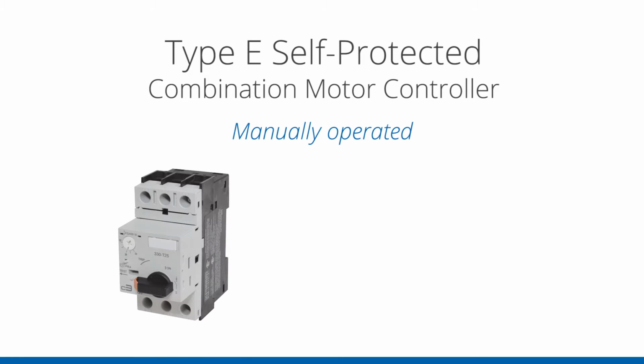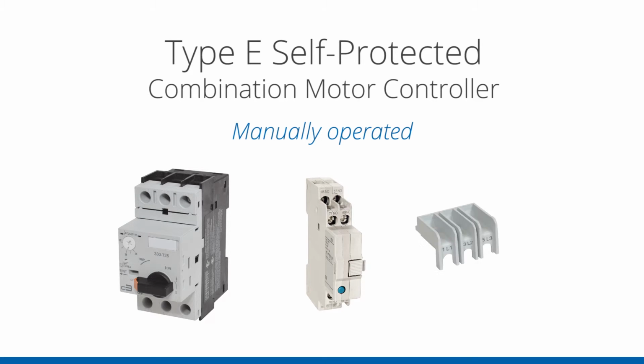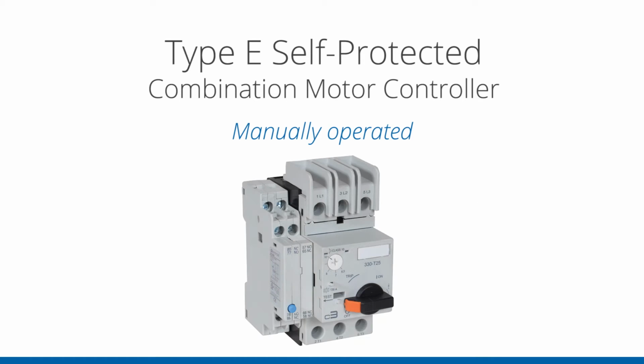Type E starters are listed as full combinations, meaning that the entire assembly is used during testing and is fully listed, and only that assembly can provide those specific ratings in a Type E application. An example of a manually operated Type E self-protected combination motor controller would include the specific motor protection circuit breaker, trip indicating auxiliary, and line side terminal barrier as a complete assembly for a particular motor rating.